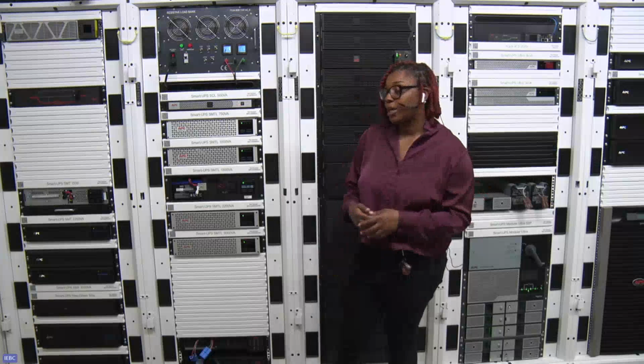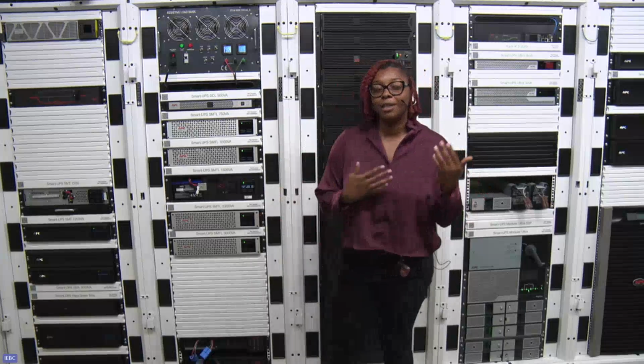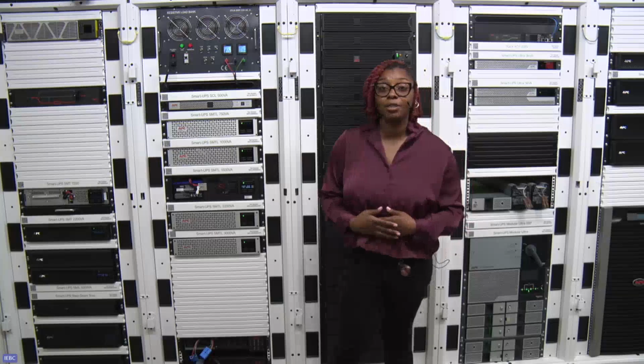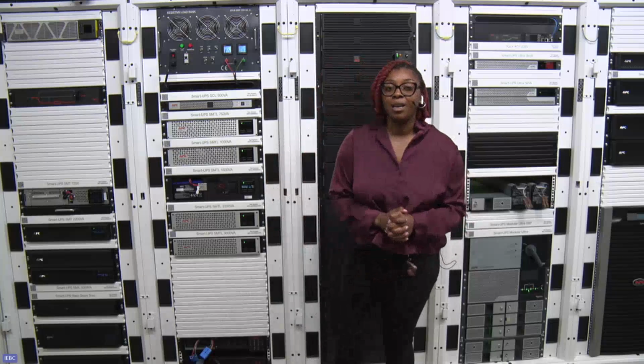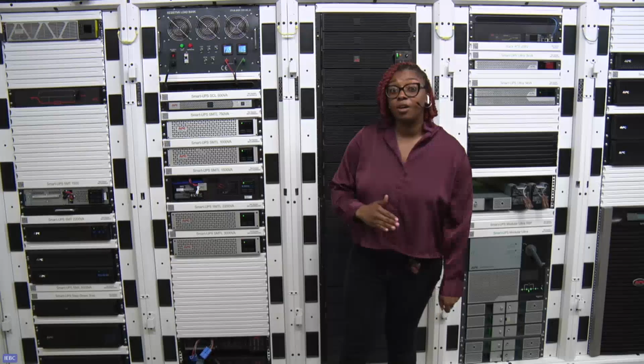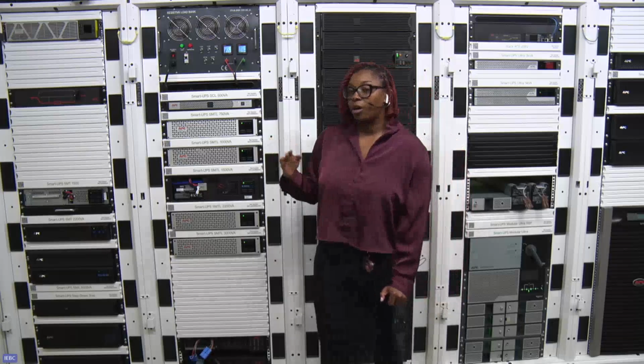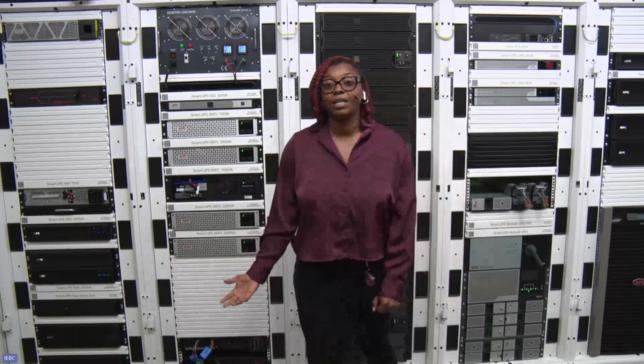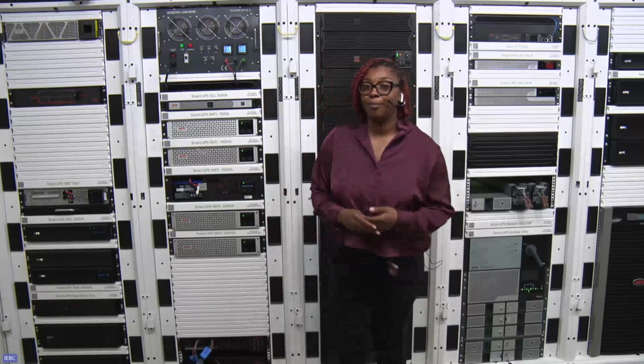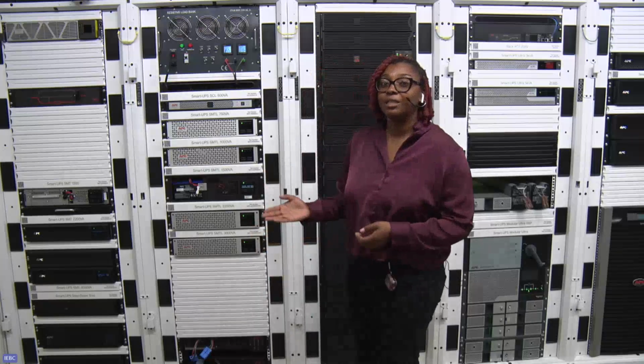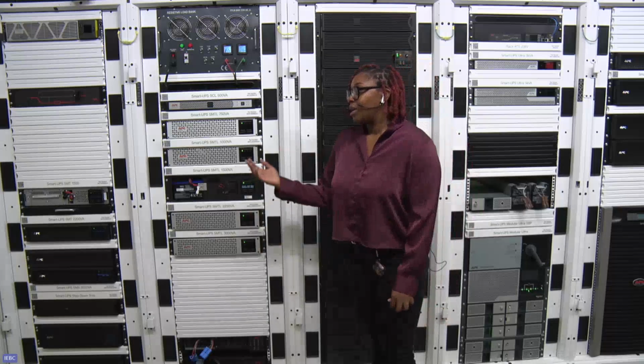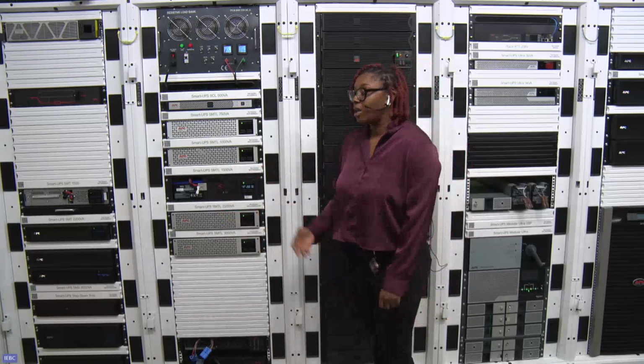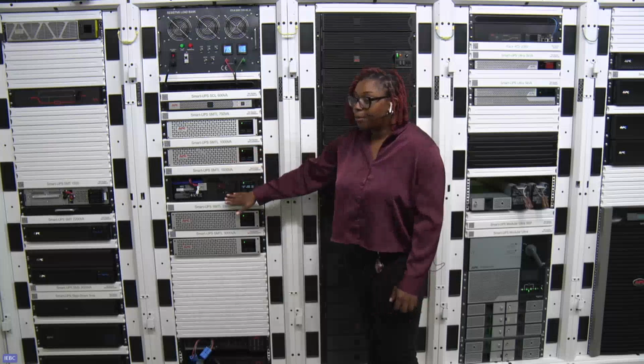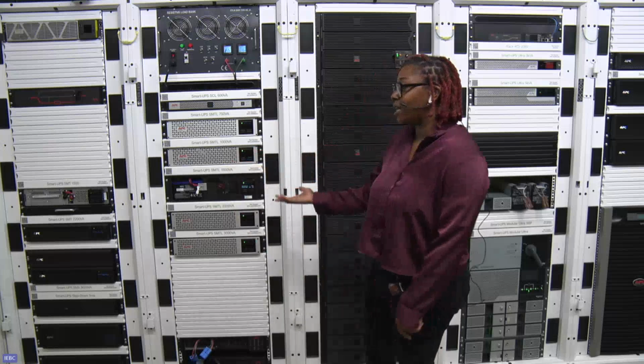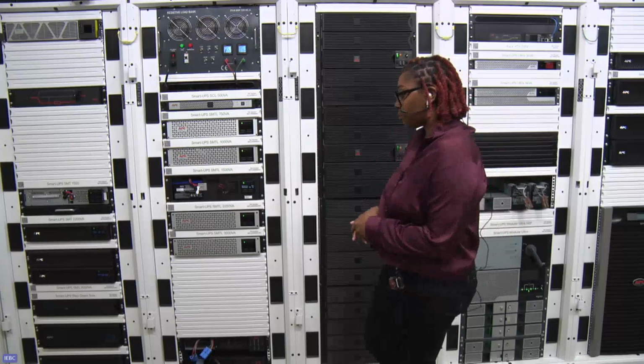Something else I want to point out are the cycles, the number of cycles. Lithium ion batteries have 10 times the amount of cycles as lead acid batteries. And what that means is how many times you can fully charge and discharge your battery. So when you are deep cycling constantly with your lead acid battery, that actually degrades the battery. And I mentioned 3 to 5 years for lifespan, but that can actually shorten it. So lots of things to think about when using lead acid batteries and a lot more maintenance involved, where lithium ion batteries are a set it and forget it type of battery solution.